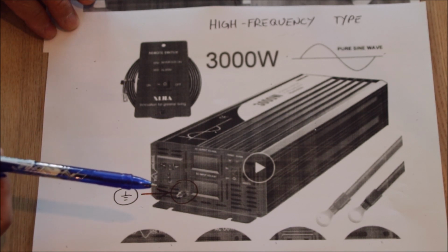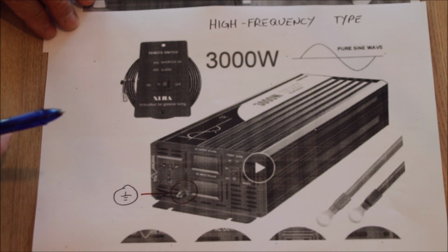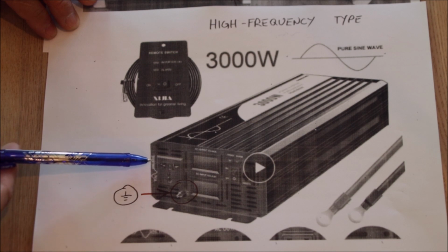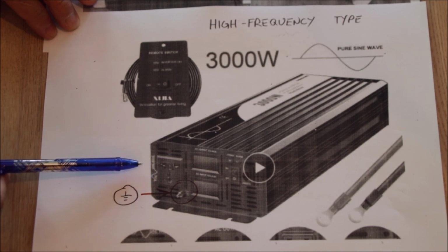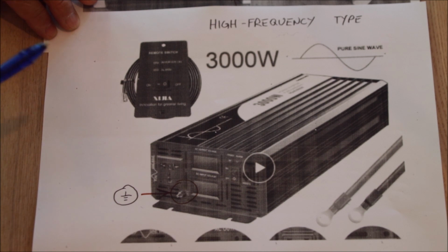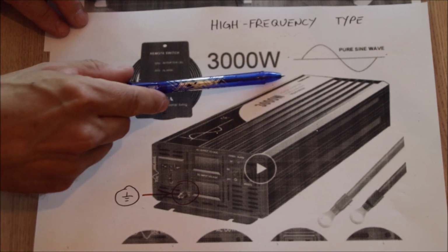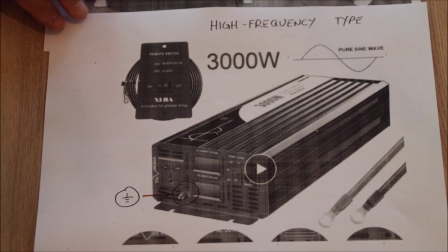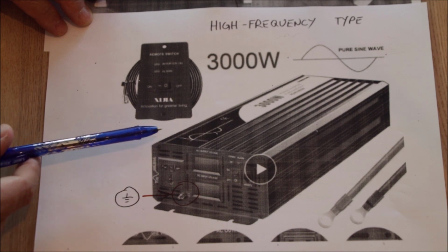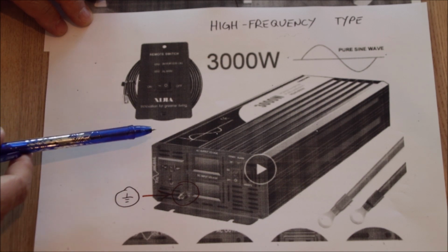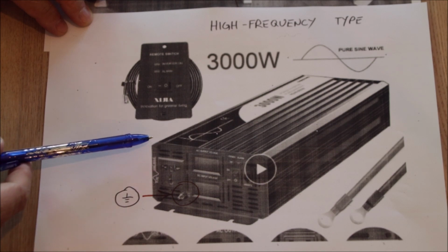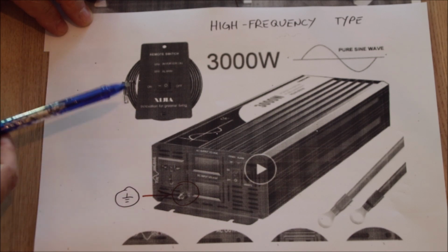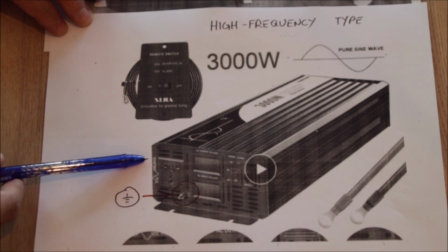High frequency or low frequency type refers to how the inverter is generating its sine wave. High frequency inverters are the cheaper version because internally they don't have big inductors which smooth out that sine wave. They generate the pure sine wave just by very quickly switching the DC on and off. This type of inverter, by design, is purely meant to be used as an IT earthing system, isolated earth. That's why they are built like this.